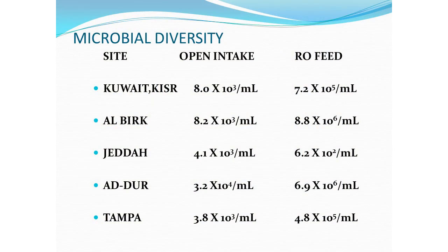And in my career, I looked at various sites in the Middle East, at Kuwait, KISR, Al Birk, Jeddah, Ad-Dur, and Tampa. And the only place that we didn't see biofouling taking place was in Jeddah. Now all these other sites were doing chlorine dechlorination.